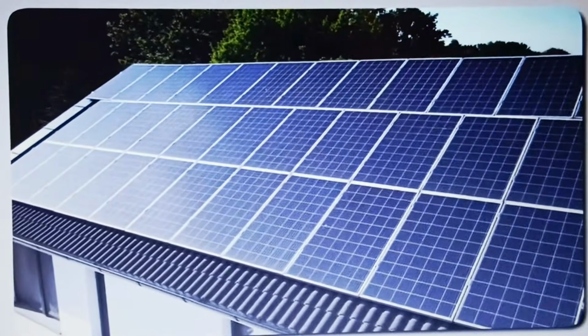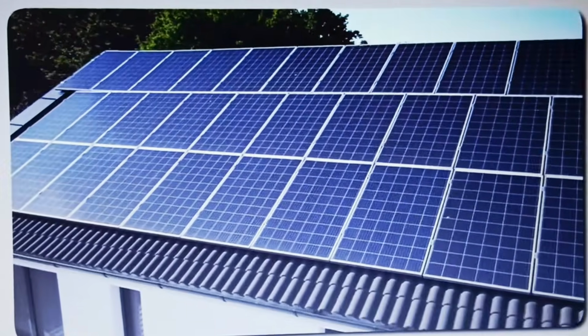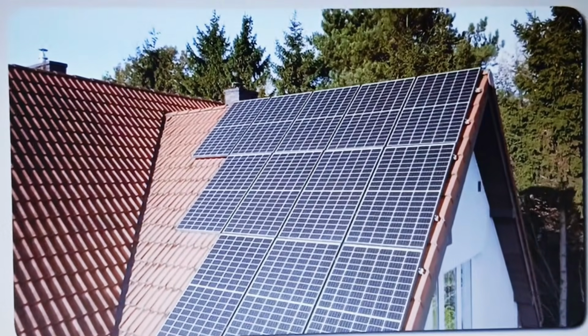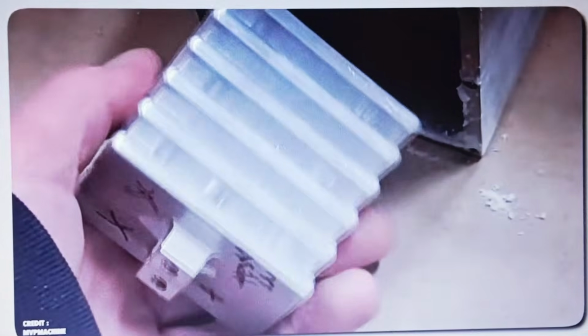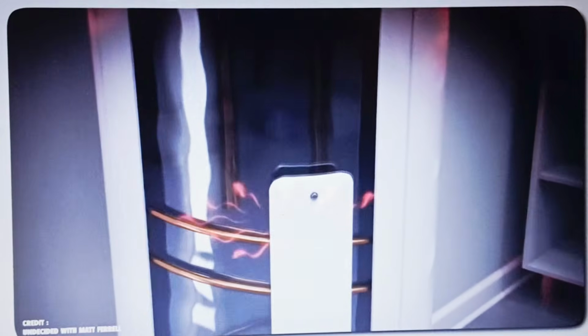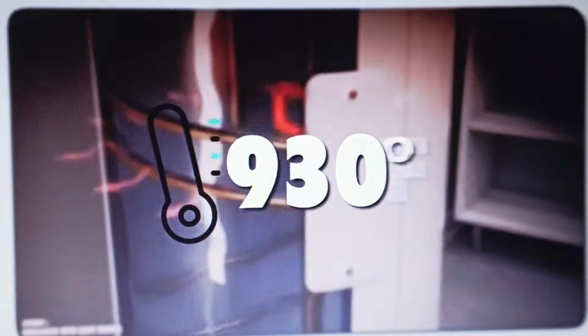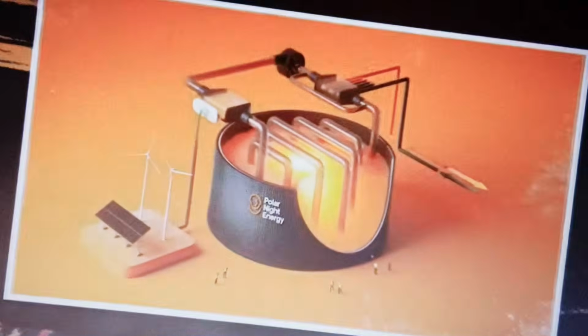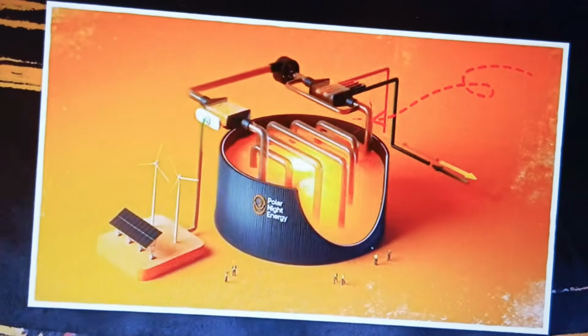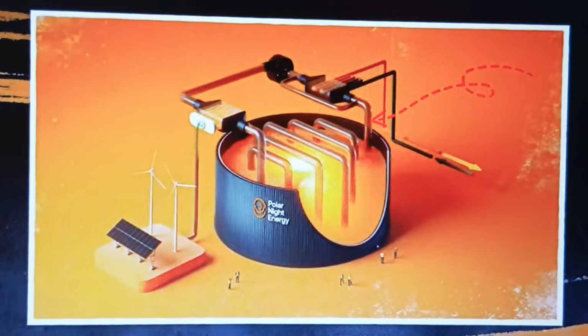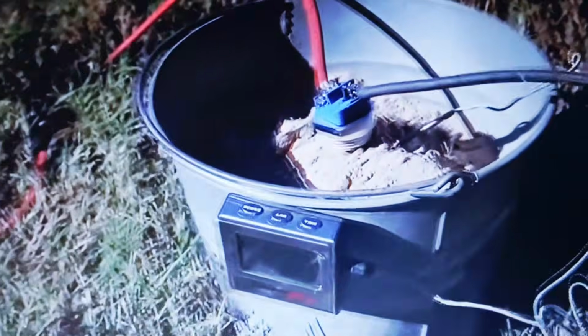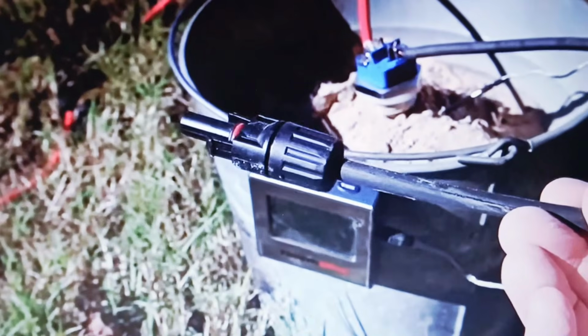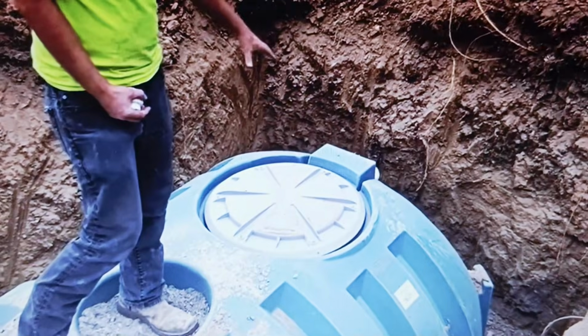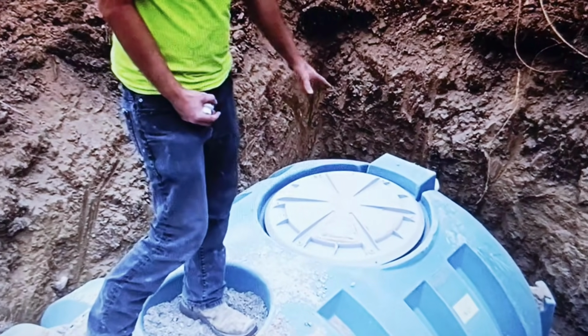During summer, when your solar panels are generating more electricity than your house can use, that surplus power, which would normally get dumped back to the utility grid for pennies on the dollar, instead gets routed into Batsand's resistive heating elements. Those elements superheat ambient air to 500 degrees Celsius. That superheated air is blown through insulated stainless steel tubes directly into a massive sealed sand container.